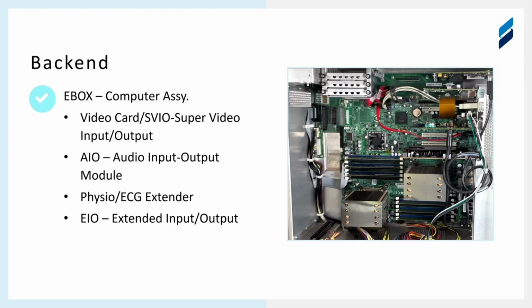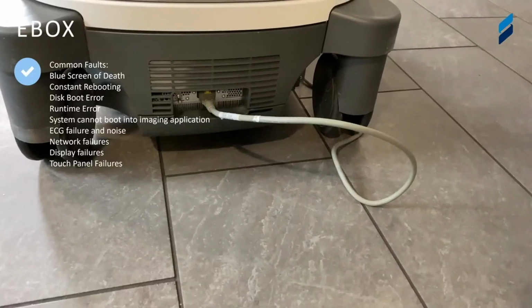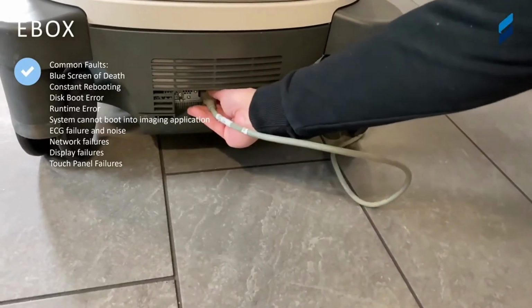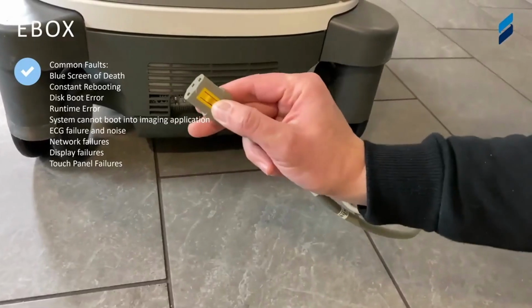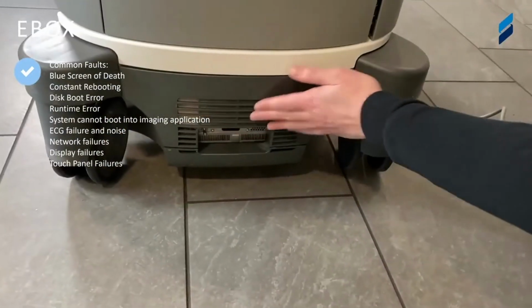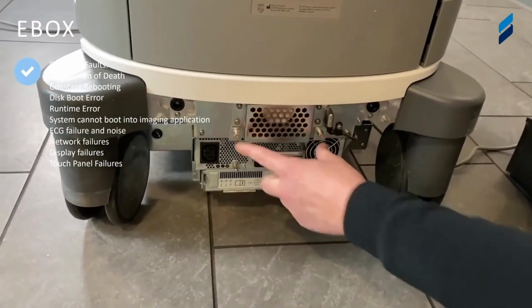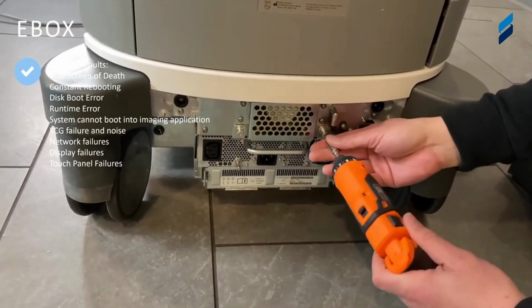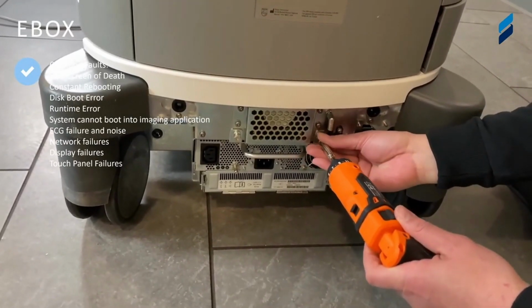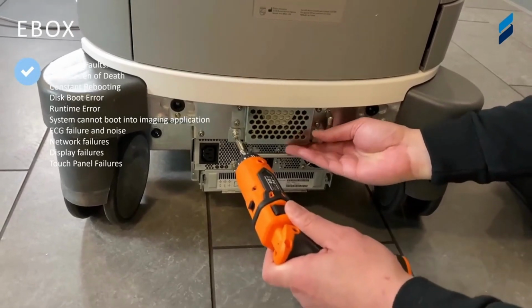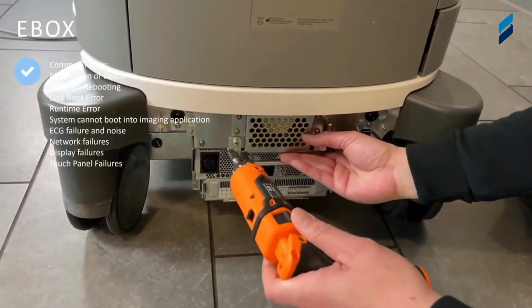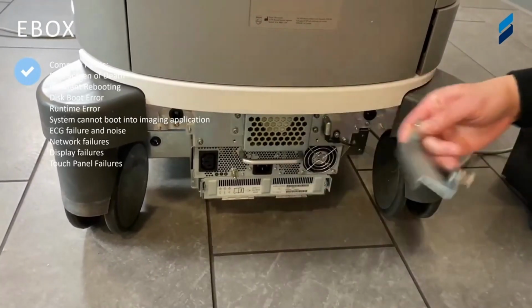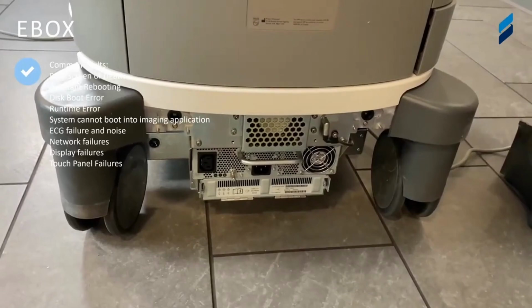So we're going to jump into how to work on an Ebox. This is disassembly to get to the Ebox. This doesn't fail too often, but it is the heart and soul of this machine. In addition to the acquisition module, really it's a computer. We're making sure all power is removed from the machine. Should be standard operating procedure when you work on any equipment. And to get to the Ebox, we must first remove the power module.